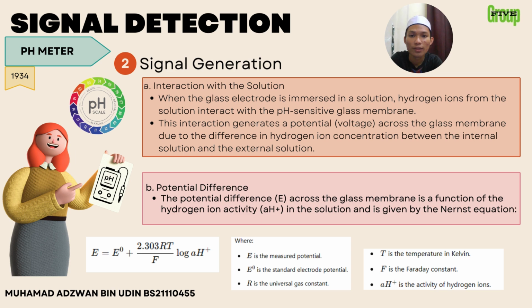Next is signal generation and interaction with the solution. When the glass electrode is immersed in a solution, hydrogen ions from the solution interact with the pH-sensitive glass membrane. This interaction generates a potential voltage across the glass membrane due to the difference in hydrogen ion concentration between the internal solution and the external solution. For the potential difference, the potential difference E across the glass membrane is a function of the hydrogen ion activity, aH+, in the solution, and it's given by the equation below.